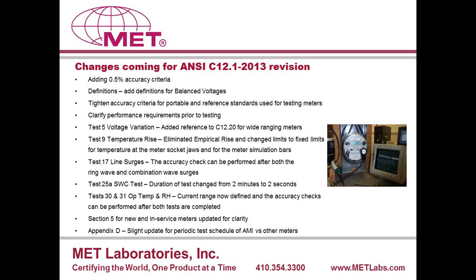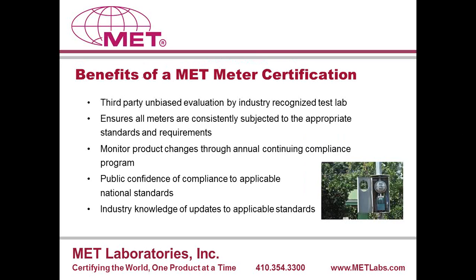Test 25, the SWC test, there was a typo in the standard. It's going to be changed from 2-minute durations to 2-second durations to bring that more in line with industry standards. Some additional accuracy checks, defined accuracy checks during the course of the operating temperature and relative humidity tests. And some additional clarity, I'll say, for in-service meter performance and criteria that you find in the back of the C12.1 standard in Section 5, along with a periodic test schedule for utilities to check meters in the field. So just a few things there that'll be updated.